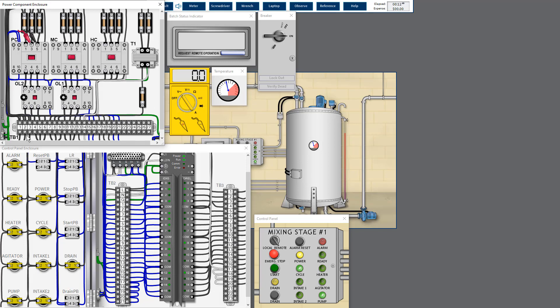Usually if you measure the three-phase wire cable and you get zero ampere for all the phases, it means most likely there's an open circuit in two phases, open circuit or loose termination in two phases out of three phases. Maybe it's because of the motor winding to winding short that causes the two phases open, or one phase having the fault in the contactor or the overload where there's an internally open circuit, and another phase maybe loose termination or maybe there's an open circuit in the fuse or wire or even inside the motor stator winding.